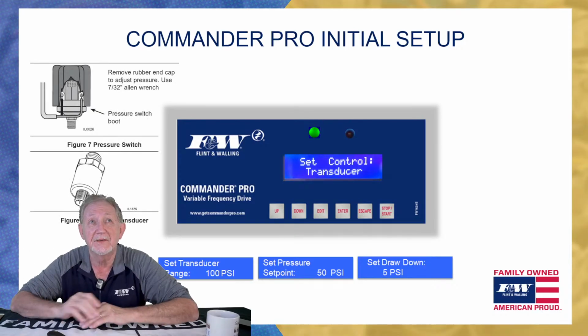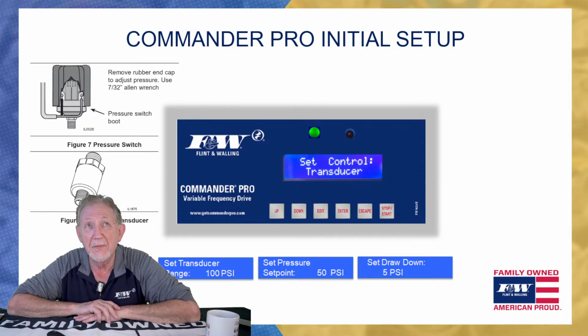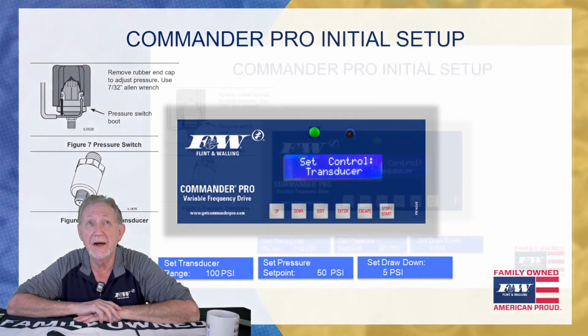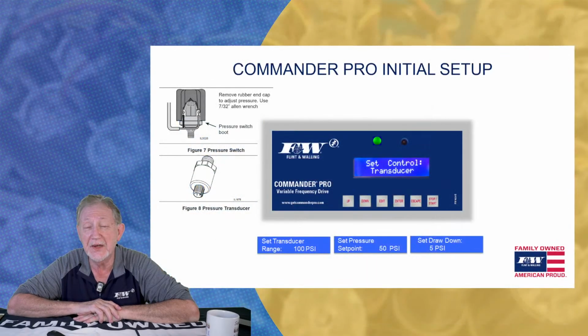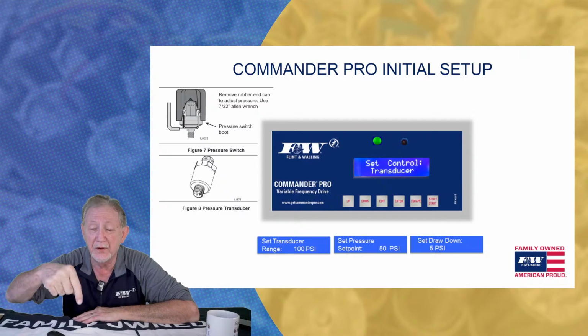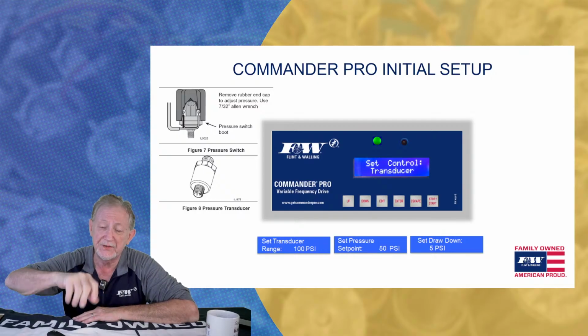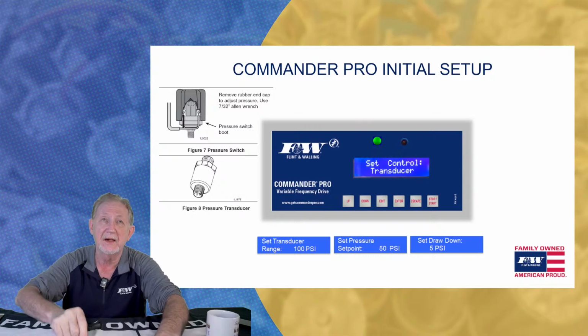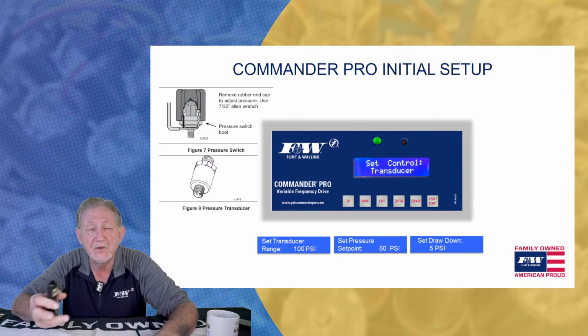This is what that transducer would look like on the bottom. The pressure switch we referred to is located up there at the top. Now with that pressure switch, to set the pressure set point, you take that rubber boot off the top of that switch, and then with a nut driver you can go down and, like a conventional pressure switch, you'll crank this thing clockwise to increase the pressure.